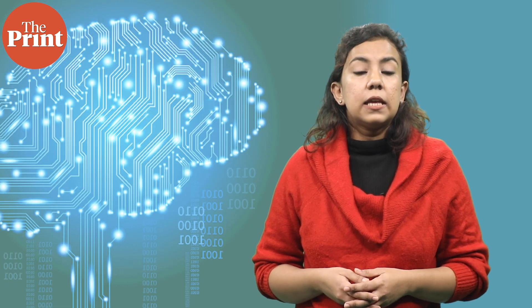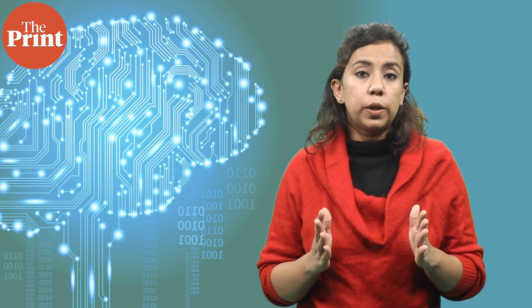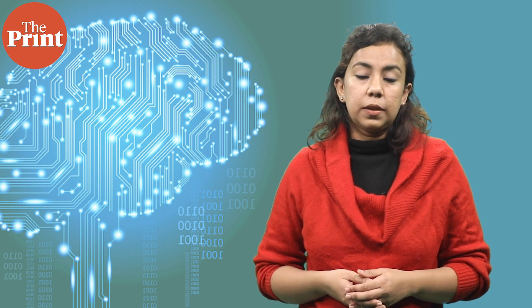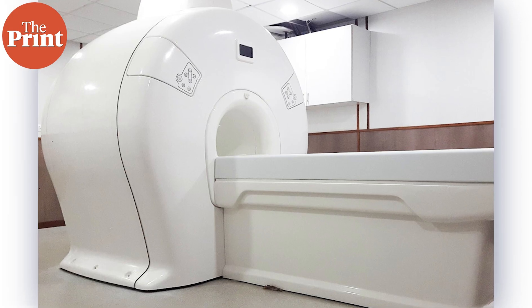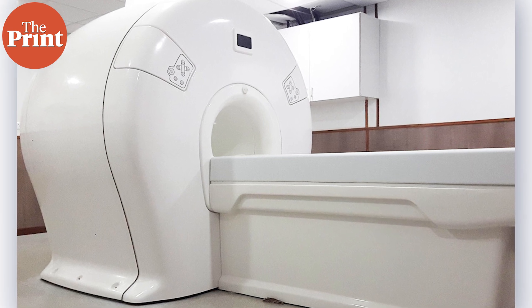Voxelgrids. This Bengaluru-based biotechnology company has developed a compact, lightweight, full-body MRI scanner that is easily portable and more affordable. The company designs instruments better suited for Indian hospitals, running on the more affordable liquid nitrogen for cooling instead of liquid helium.